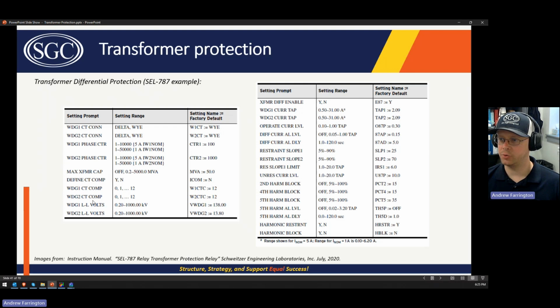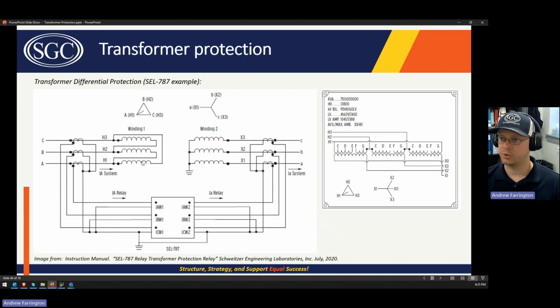Then we have the winding 1 and winding 2 compensation settings. You can see that the available range is between 0 and 12. We'll talk about that in the coming slides, so just put that on hold for now. But that's looking at the phase angle shift for a DY1 or DY11 transformer, and this is where we account for that. Then we have the winding 1 line-to-line voltage and the winding 2 line-to-line voltage. For our transformer, winding 1 is the high voltage winding, which is 13.8 kV, and then the low voltage winding is 4160. So our settings would be 13.8 kV and 4.16 kV.